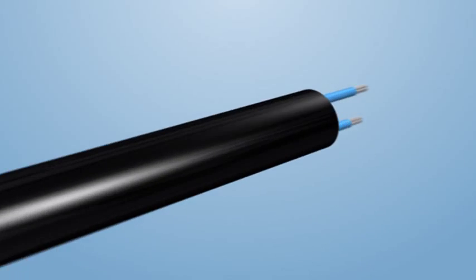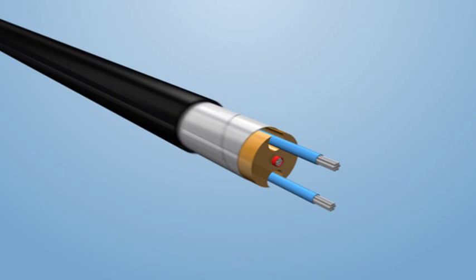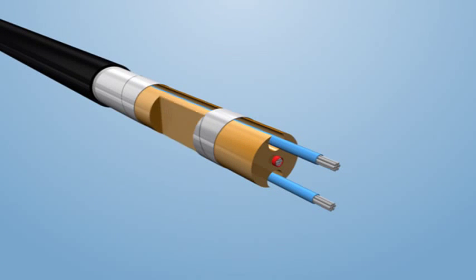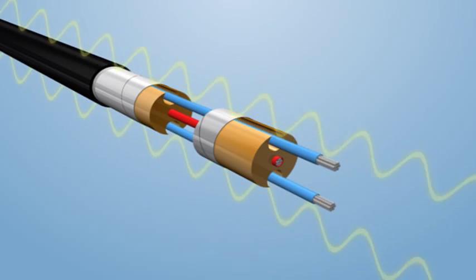Inside the cable, a pair of precision conductive wires are arranged within a static magnetic field created by the flexible ceramic magnetic core. When these conductors vibrate, the interaction with the magnetic field generates an electrical signal which accurately represents the mechanical vibration which caused it.